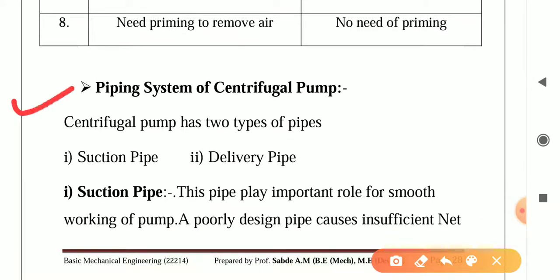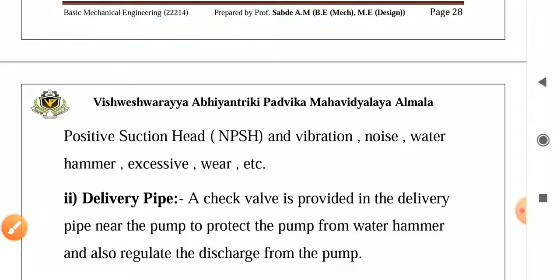This is the piping system of centrifugal pump. There are mostly two piping systems: suction pipe and delivery pipe. What is suction pipe? This pipe plays an important role for smooth working of the pump. A poorly designed pipe causes insufficient positive suction head, that is NPSH, and vibration, noise, water hammer, excessive wear, etc.